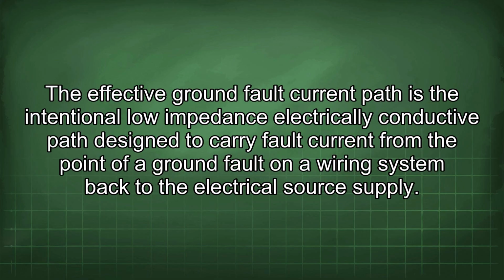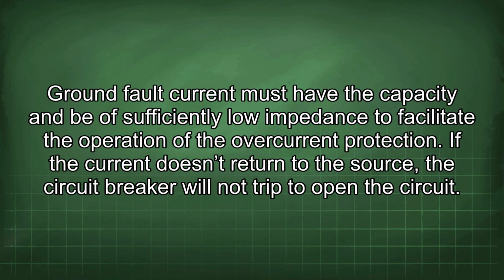The effective ground fault current path is the intentional low impedance electrically conductive path designed to carry fault current from the point of a ground fault on a wiring system back to the electrical source supply. Ground fault current must have the capacity and be of sufficiently low impedance to facilitate the operation of the overcurrent protection. If the current doesn't return to the source, the circuit breaker will not trip to open the circuit.